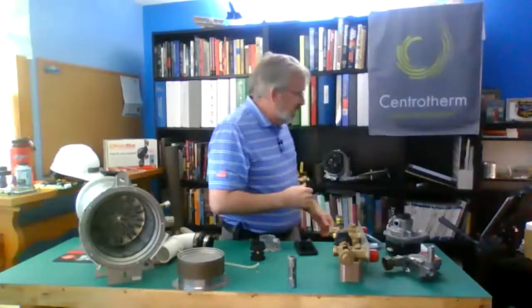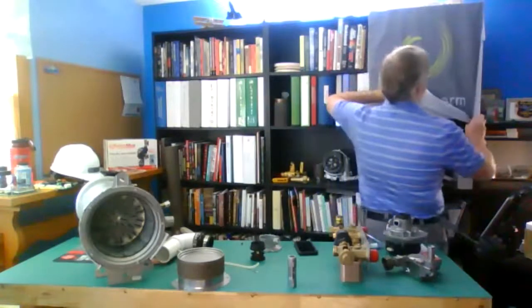So if everything's good, light off was good, no noise, good flame pattern, good flame signal, good CO, take your number. And that's really going to be your number. If you hit all of those marks, what's your number? So let's just, we're back in the natural gas conversation. Let's just say that my natural gas CO2 at this point in time is 9.6. If I'm 9.6 at high fire, at low fire, I want to be maybe 0.2 below that. So 9.4 is where I would be at low fire. On propane, I'm probably somewhere between 10 and 11% is my combustion. So I might be a 10.7 at high fire, and I might be a 10.5 at low fire. I want to keep them close together. And really the reason for that is, I didn't get this thing set so I can show you guys.